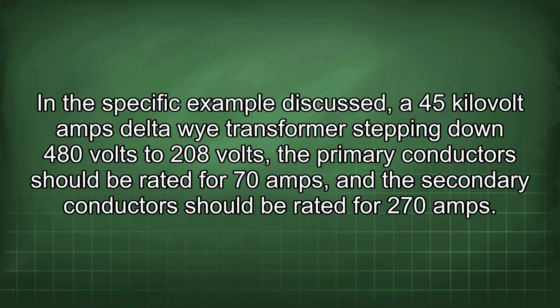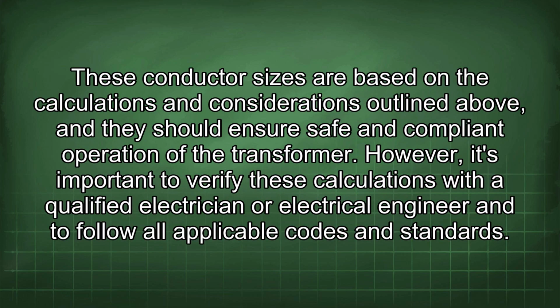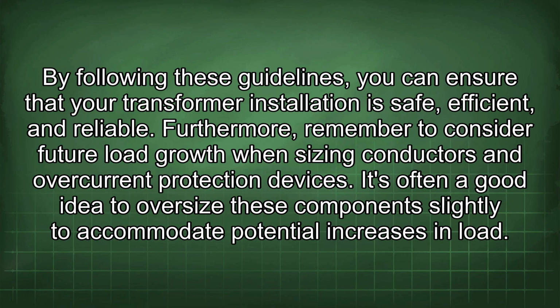In the specific example discussed, a 45 kVA delta-Y transformer stepping down 480 volts to 208 volts, the primary conductors should be rated for 70 amps, and the secondary conductors should be rated for 270 amps. These conductor sizes are based on the calculations and considerations outlined above, and they should ensure safe and compliant operation of the transformer. However, it's important to verify these calculations with a qualified electrician or electrical engineer and to follow all applicable codes and standards. By following these guidelines, you can ensure that your transformer installation is safe, efficient, and reliable.